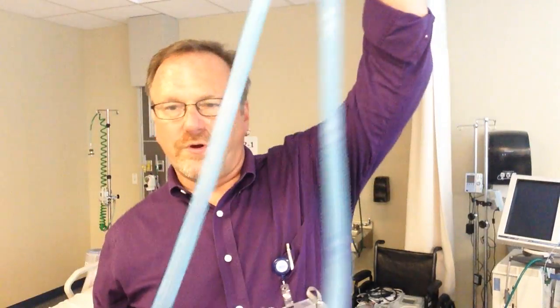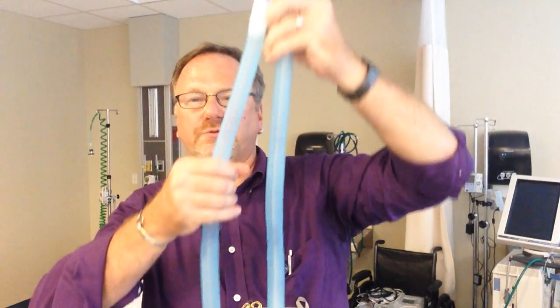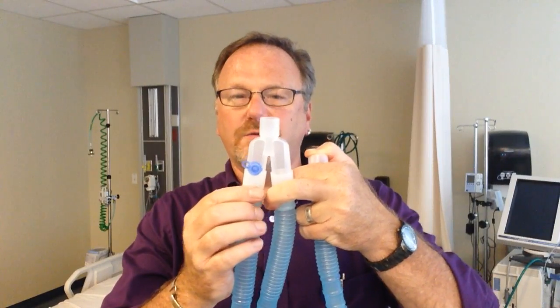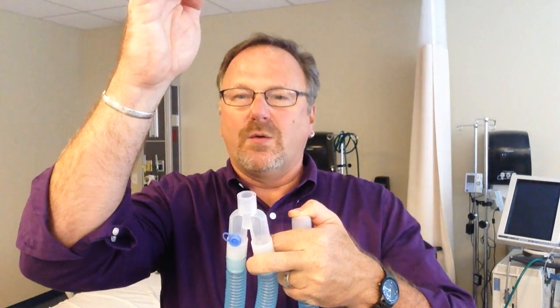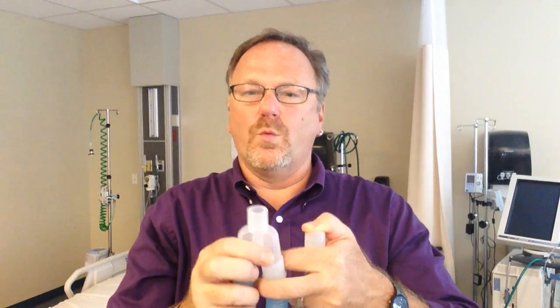So you come up the inspiratory side. It'll come from the ventilator. The breath will travel up the inspiratory side, go to here, go to the patient, because right now my expiratory limb, my expiratory valve is closed. So if I'm blowing gas or air in here, the only way to go is into my patient. Then the air goes into the patient. When my expiratory valve opens, the patient will exhale passively. The recoil, the compliance, the elasticity of the chest, the lungs, the weight, everything is a passive exhalation.